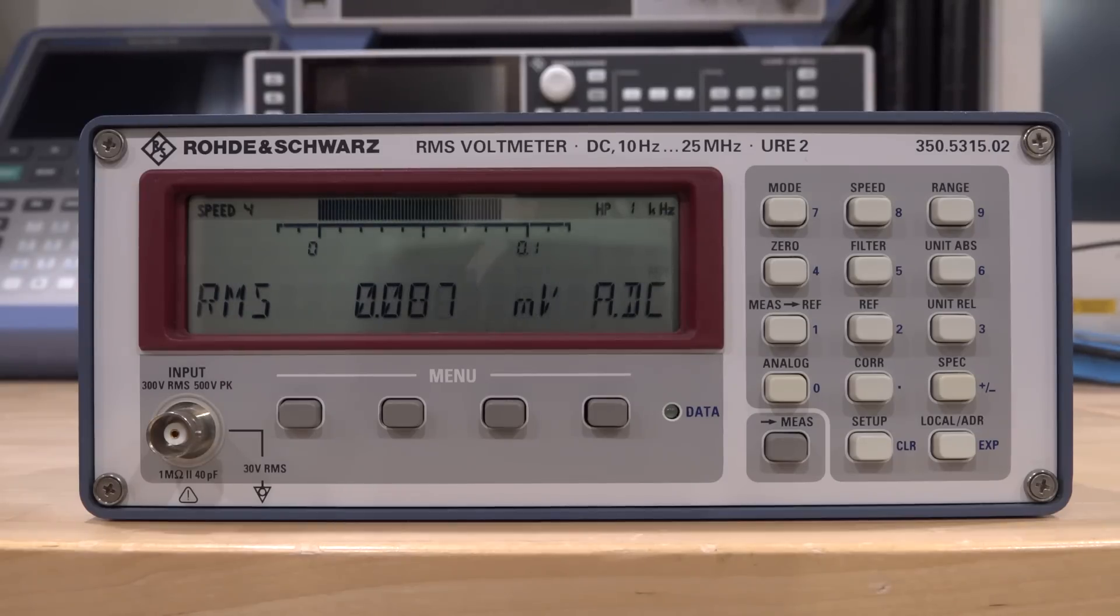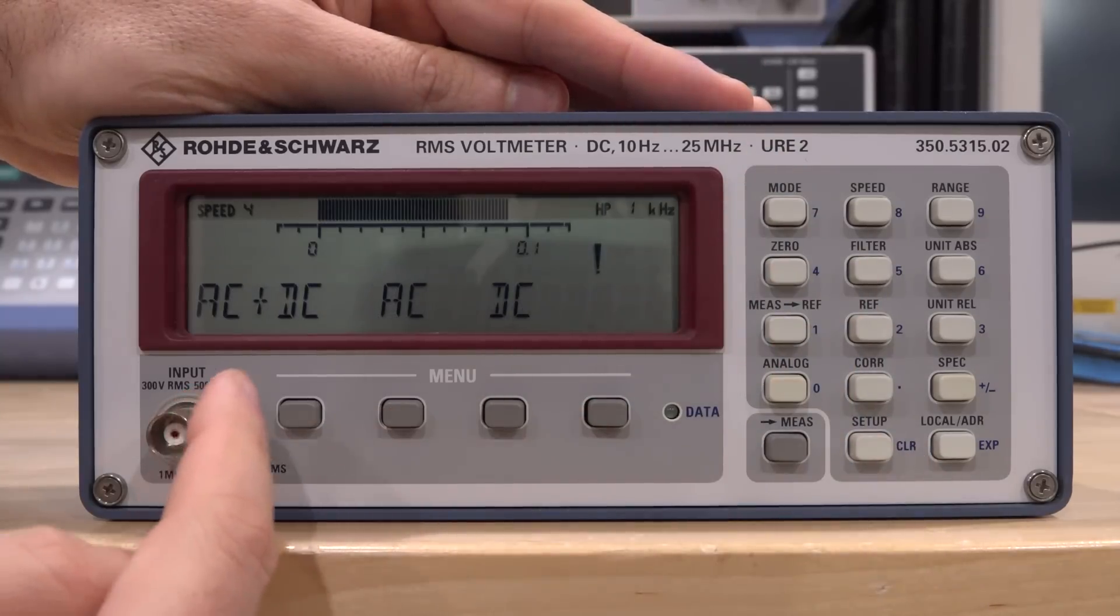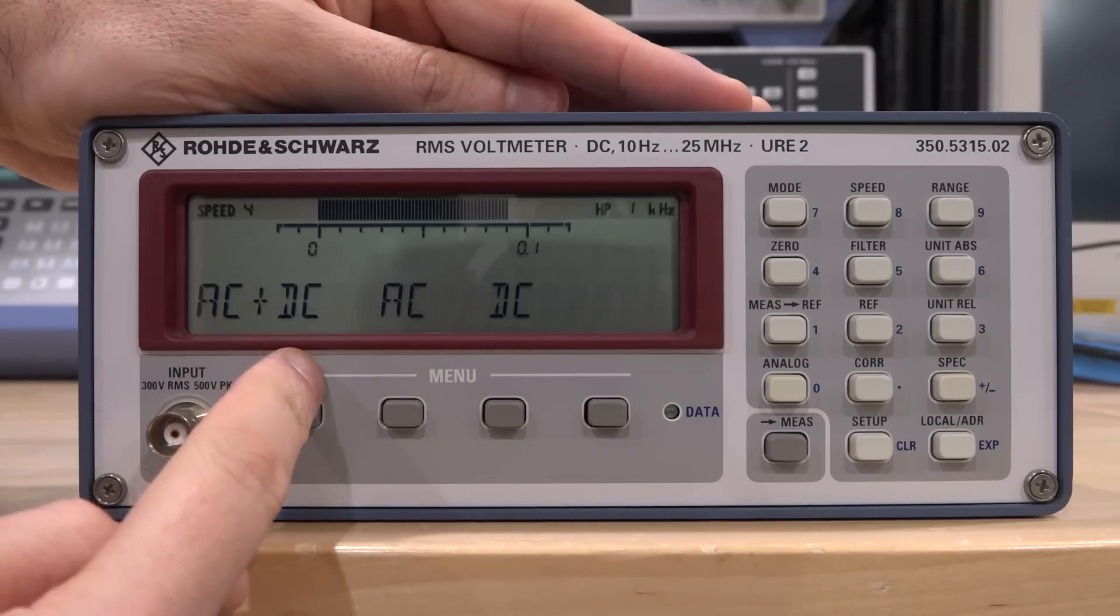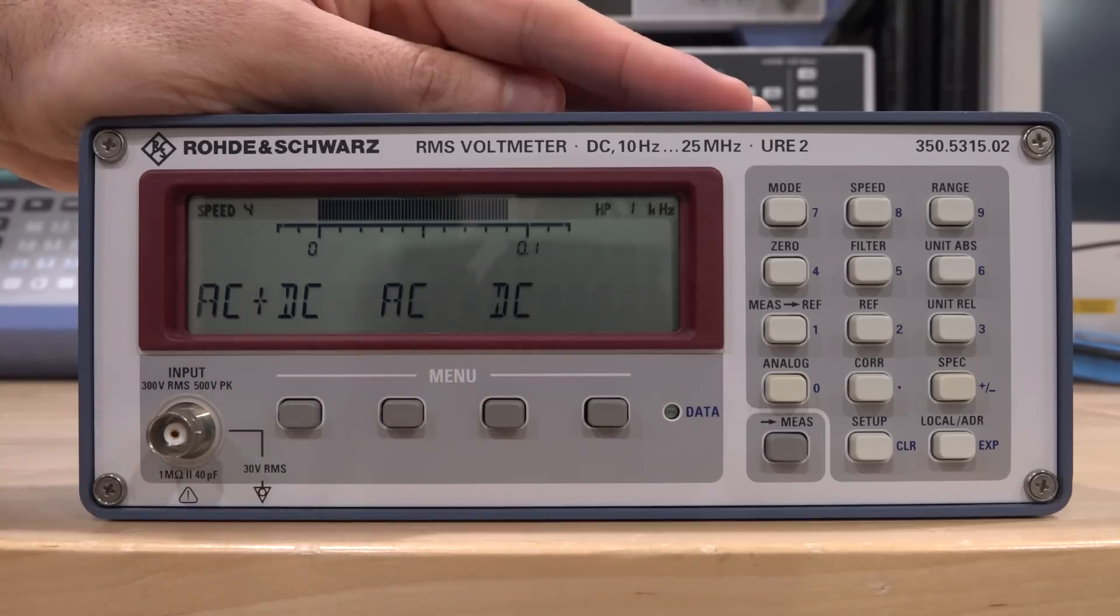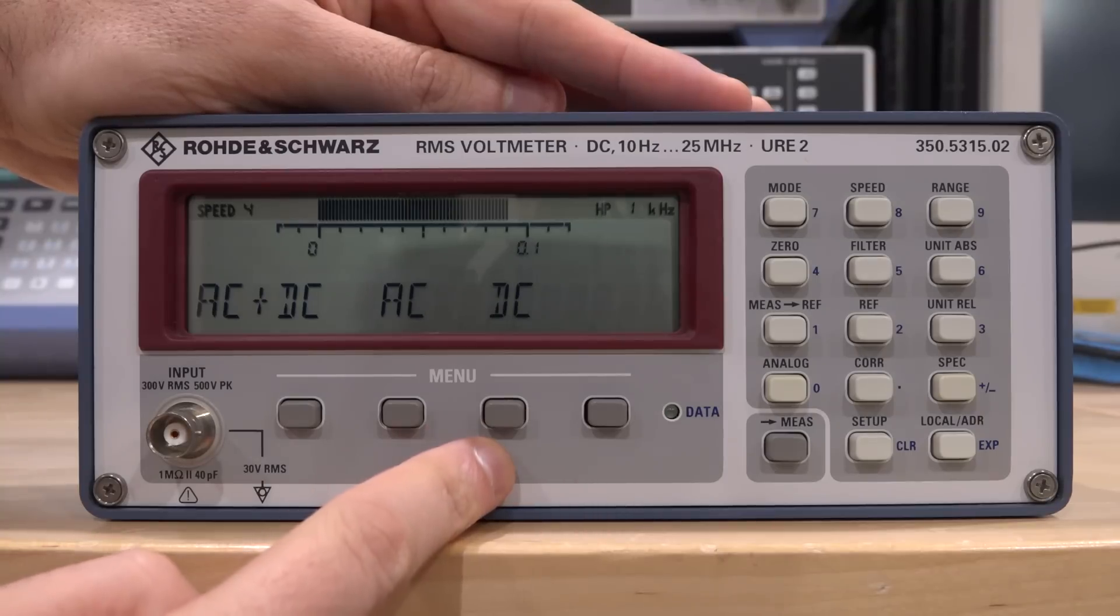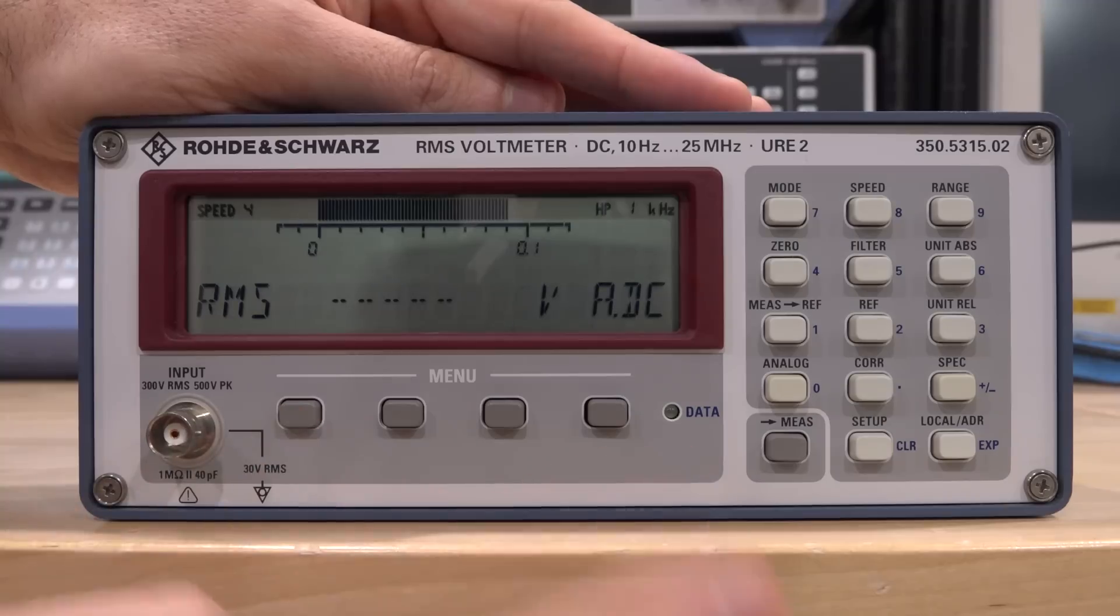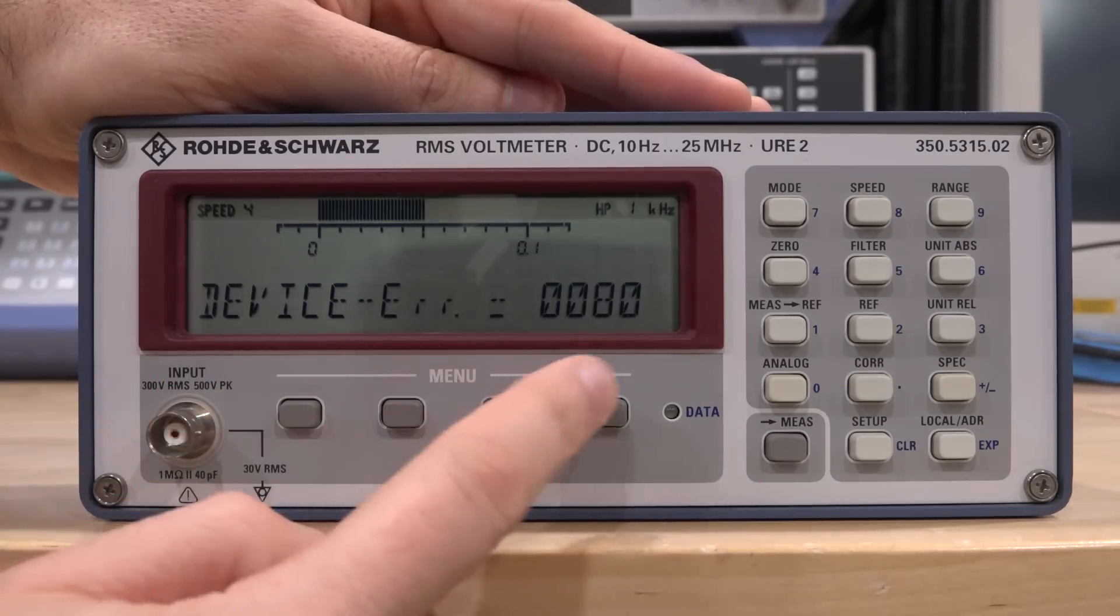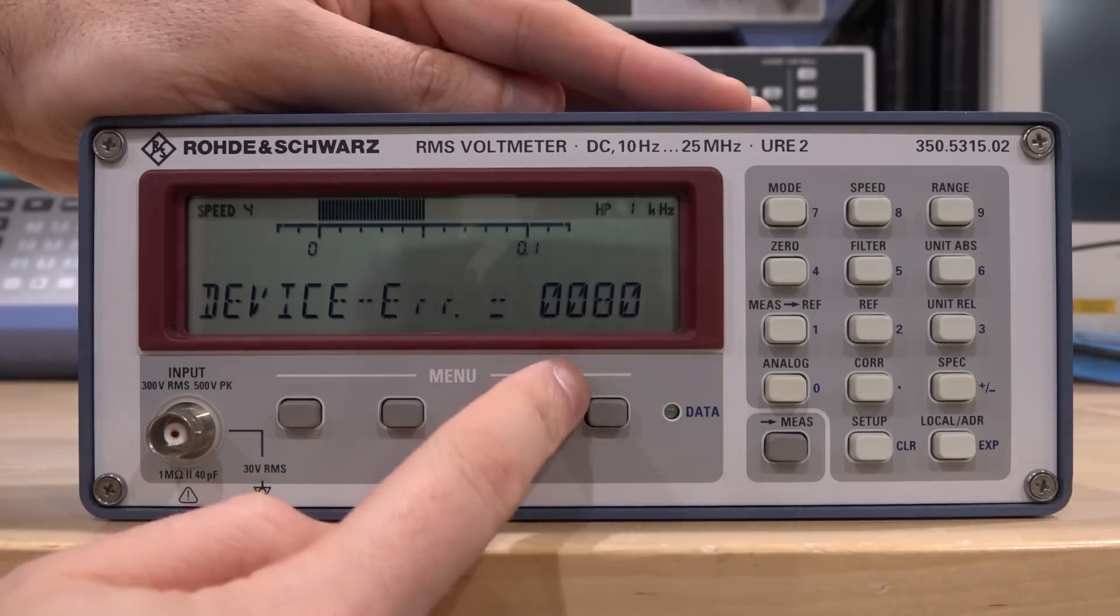It does pass its own internal self-test. Now if I go under mode, you can see it has a few different modes: you can measure DC, AC, or AC plus DC. That tells us there is more than one path. It's not able to give me any DC measurements, but it does return the correct AC measurement. Every once in a while when I turn it back on and off—there you go—that's the error: Device Error 0080.